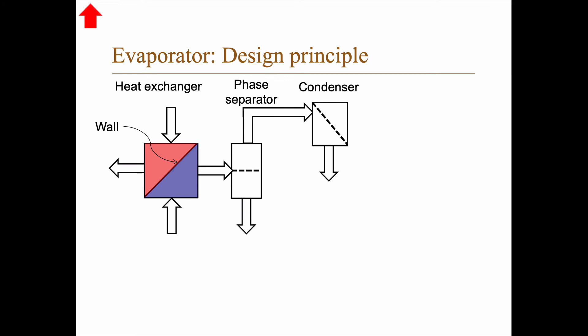So when we talk about this design principle, the condenser here is what determines the pressure on the feed side. And the pressure on the steam side is what determines the condensation temperature on the steam side.